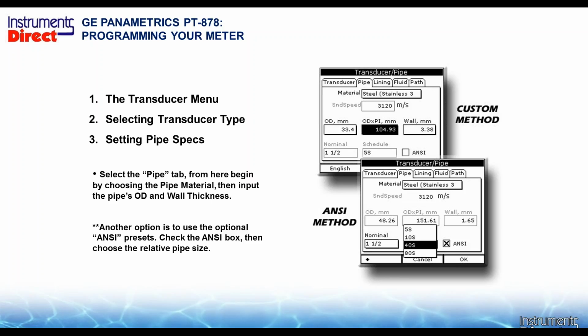The OD is going to be 3.5. So if you're typing the raw numbers in there, put the correct pipe outside diameters there. We ship every meter here with an ANSI pipe chart book, or it's downloadable from the website there. Put in good data, you'll get good data output.